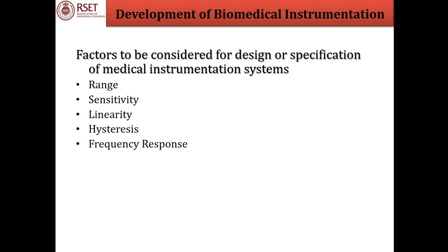Now, the frequency response of an instrument is its variation in sensitivity over the frequency range of the measurement. It is very important to display a wave shape that is a faithful reproduction of the original physiological signal.